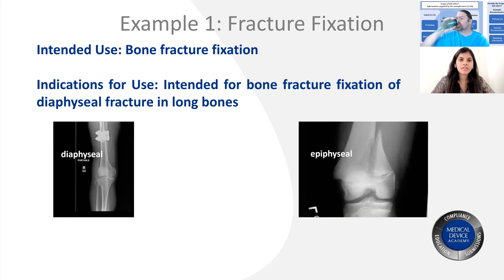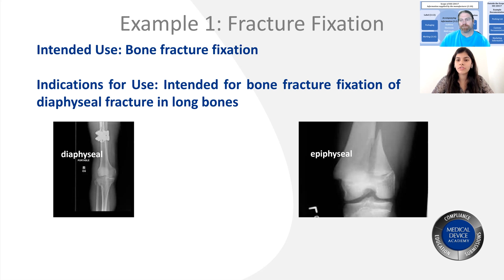As Rob explained in the previous slides, let's move on to one of the examples. One example we have taken is for fracture fixation, from the FDA guidance. The intended use mentioned here is 'bone fracture fixation.' You can see they have not mentioned the location where it will be used, the environment of use, or whether it will be sterile or non-sterile. They've simply mentioned that it's going to be used for fracture fixation.